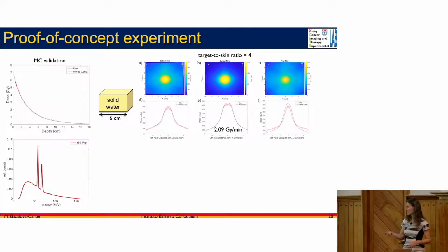And this is how we measure dose. So these are the experimental results from the solid water phantom. And you see these were pieces of film placed at different heights in the phantom. So this one was at the center, this one was at the bottom, and this one was at the top. And we were again able to get a really good agreement between the measured dose that's shown in red, with the error bars, and with Monte Carlo simulations. So the dose rate was about 2 gray per minute, which is of course quite high.